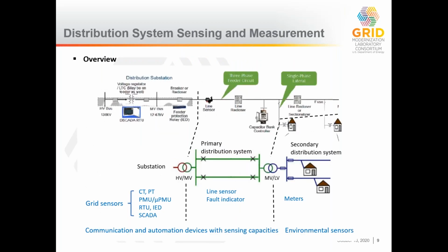So I'm summarizing here the types of sensors you see at different levels. Grid sensors include things like current transformers and potential transformers at the basic level, phasor measurement units and micro phasor measurement units, which measure voltage and current, magnitude and phase angle, giving you directional flow information to work out deviations and things like power flow from the phase angle data.